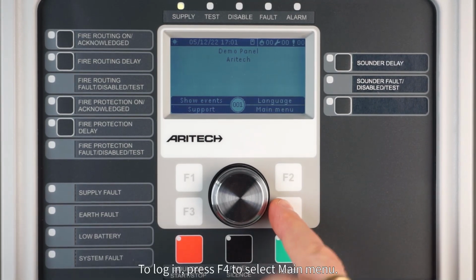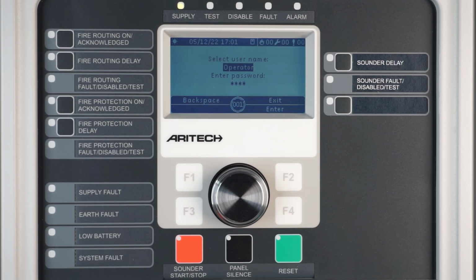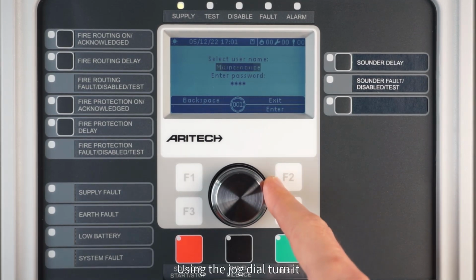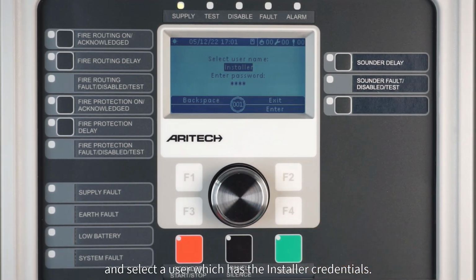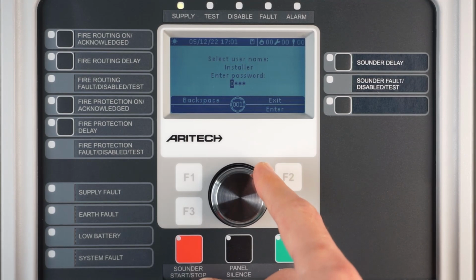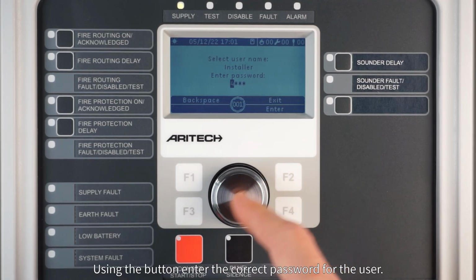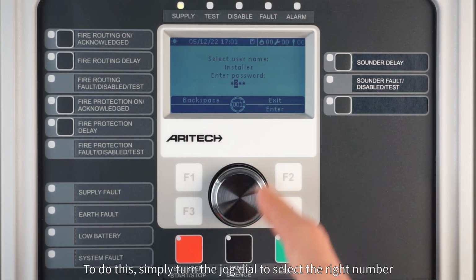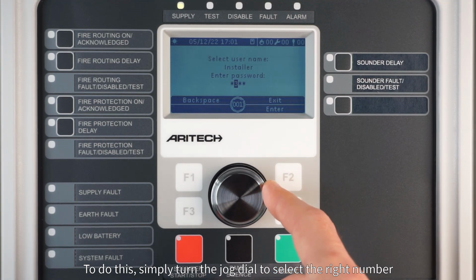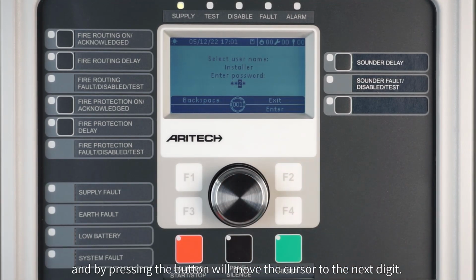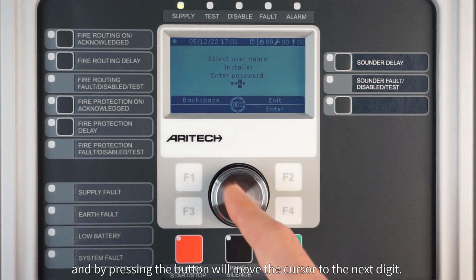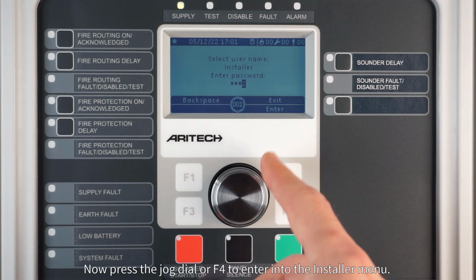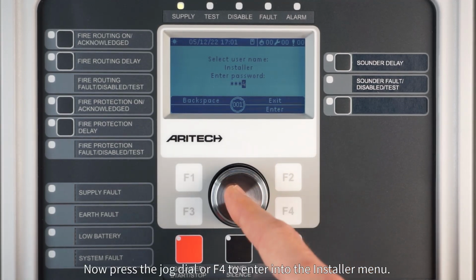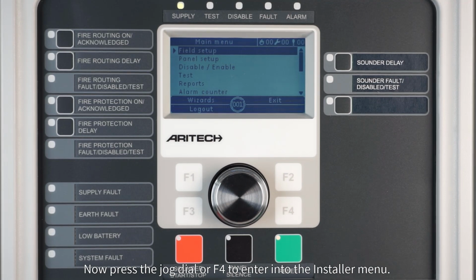To log in, press F4 to select Main Menu. Using the jog dial, turn it, and select a user which has the installer credentials. Now press the jog dial to go to the password option. Using the button, enter the correct password for the user. To do this, simply turn the jog dial to select the right number, and pressing the button will move the cursor to the next digit. Now press the jog dial or F4 to enter into the installer menu.